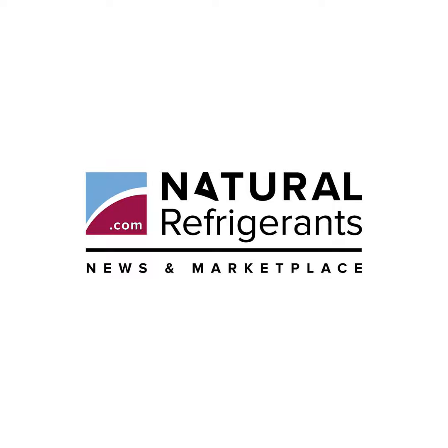In February, HYTING commissioned its first catalytic hydrogen air heating system in a new industrial facility in Offenbach, Germany. Flusys, a producer of pumps and fluid systems for industrial applications, installed a hybrid heat pump/catalytic hydrogen system to heat its 1,000 cubic meters, 35,300 cubic feet, production space with the 10 kilowatt, 2.8 tons of refrigeration, HYTING unit supporting peak heating demand. The interview has been edited for length and clarity.